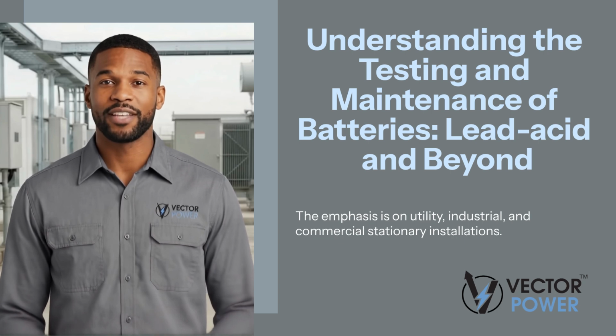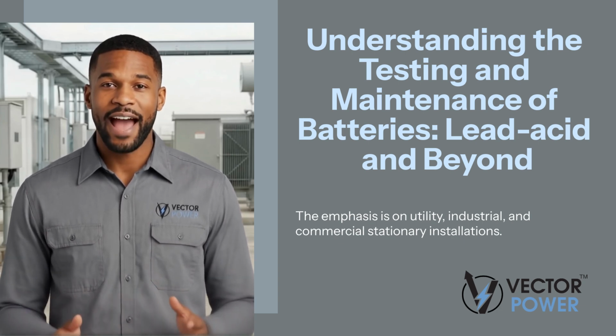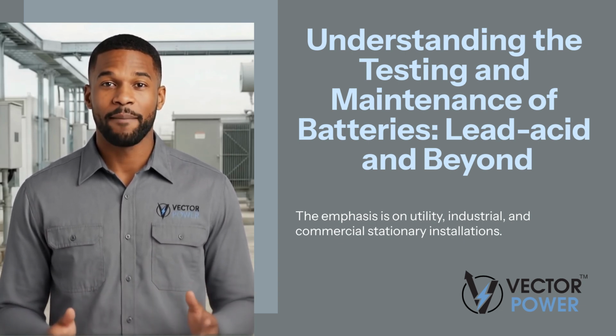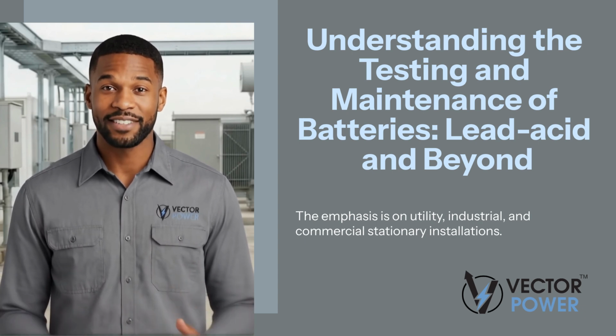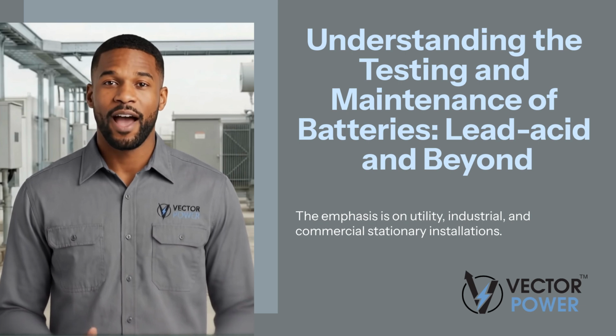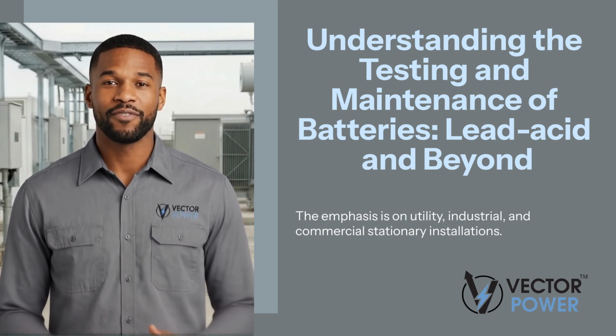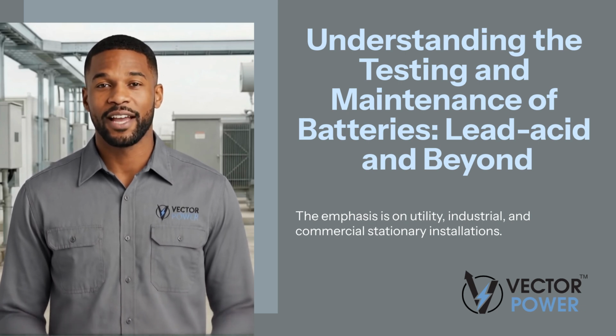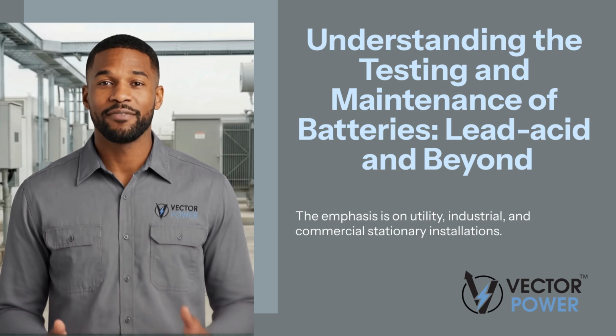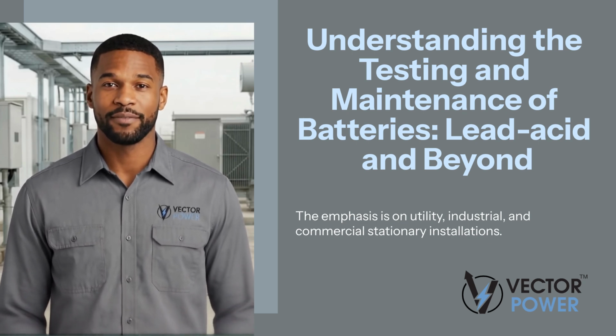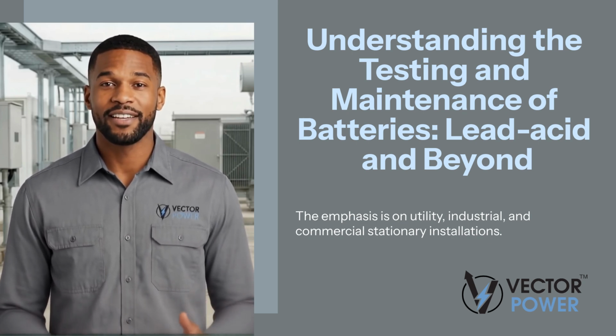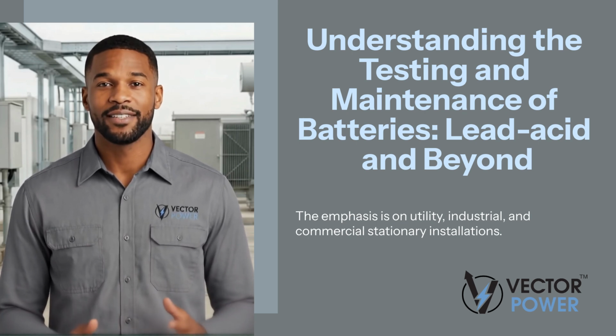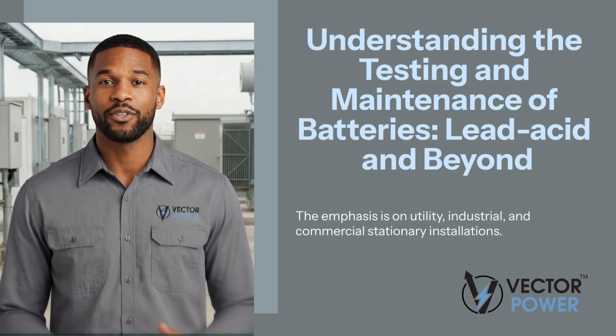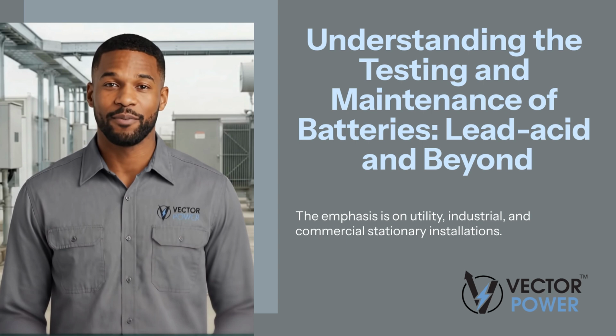The course explains how battery chemistries differ: lead acid, nickel cadmium, lithium ion, flow batteries, and high temperature, such as sodium sulfur, how those differences drive failure modes and diagnostics, and how to build a defensible maintenance strategy that integrates standards such as NFPA 70B electrical maintenance programs, NFPA 70E electrical safety controls, and NFPA 855 along with UL 9540 and UL 9540A system safety considerations.